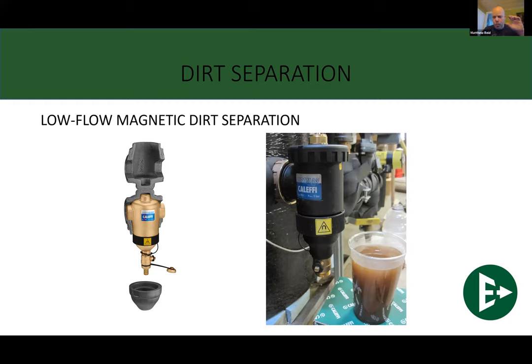So let's talk about the magnetic separation and why it even exists in the first place. Again, ferrous metals, as we discussed, exist in almost every hydronic system. And every ferrous metal is going to give off something called magnetite. Now, magnetite's a real tricky son of a gun. That 5 microns that I told you about that a standard dirt separator will catch, magnetite's much smaller than that. In water, it almost looks like it's completely dissolved. It's extremely small. And the only way to catch that we found in modern hydronic systems is with magnetic separation.